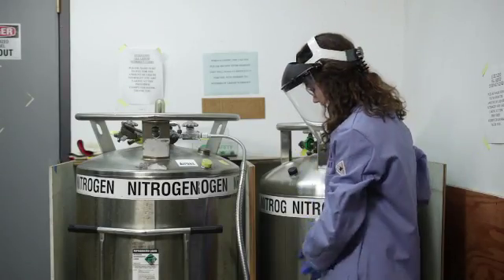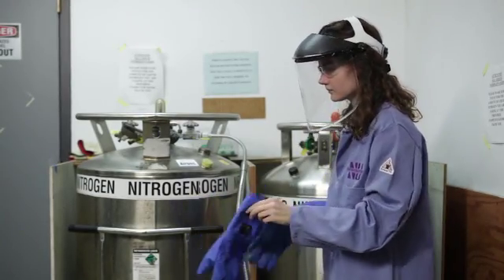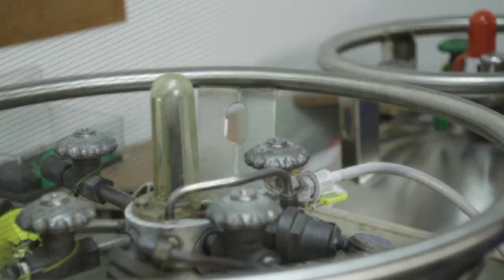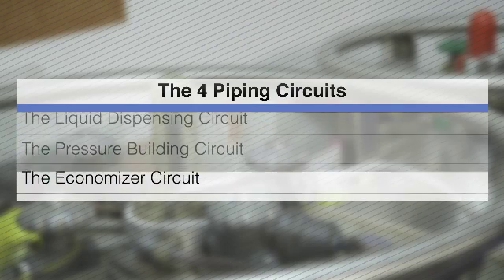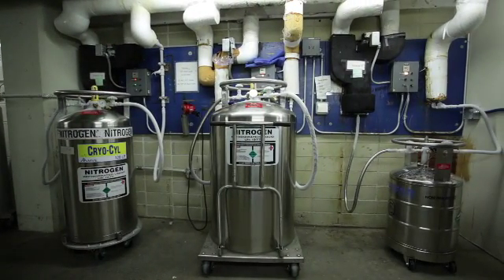Always wear appropriate personal protective equipment before withdrawing liquid nitrogen from a tank or withdrawing cryotubes. Depending on tank style, there may be four different piping circuits on a liquid nitrogen tank: the liquid dispensing circuit, the pressure building circuit, the economizer circuit, and the gas use circuit. Consult the tank manufacturer's operating manual and get familiar with the functioning of the regulators, valves, and piping circuits.